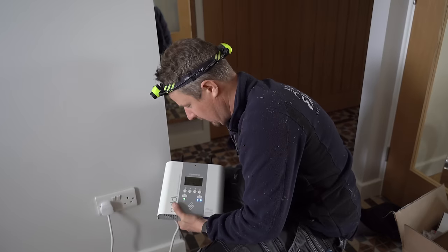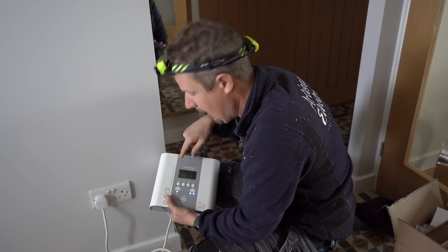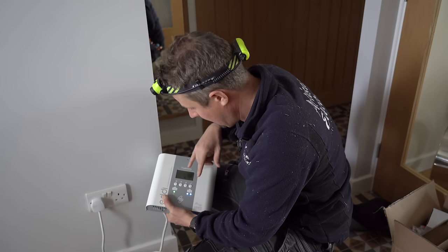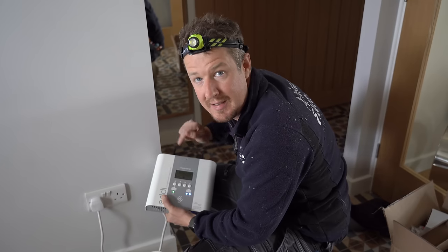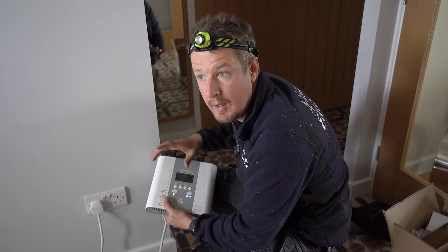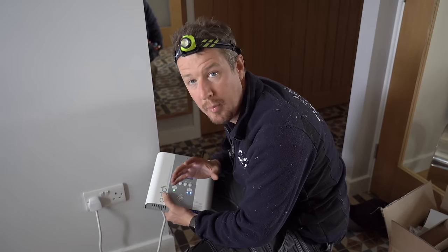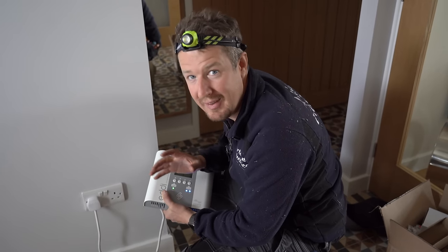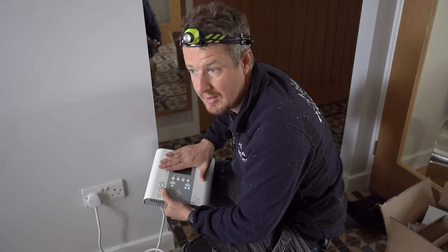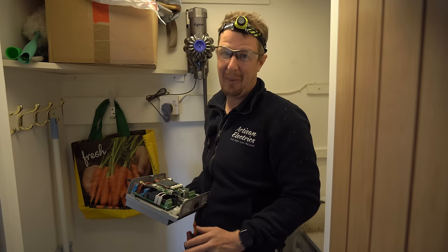A key tip with this setup: if you're only using the Harvi, you need to turn off the internal CT connection in the Eddi's menu. By default it's configured to use the hardwired grid CT, so you have to switch that off, then go to the device menu, select the Harvi, and select which CTs are connected to the Harvi. Once I did that it worked properly — that was puzzling me for a while.